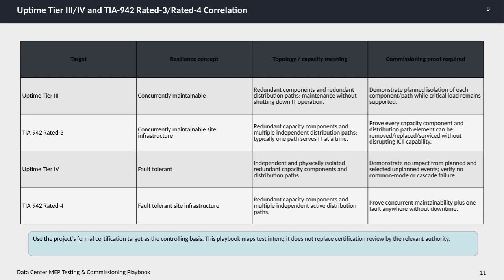On this slide, we're looking at the correlation between Uptime Tier 3 and 4 standards and the TIA 942 rated 3 and rated 4 classifications, focusing on data center mechanical, electrical, and plumbing testing and commissioning. Starting with Uptime Tier 3, it emphasizes concurrent maintainability. This means the data center has redundant components and distribution paths, allowing maintenance work without shutting down IT operations. To commission for this tier, you need to demonstrate planned isolation of each component or path while still supporting the critical load.